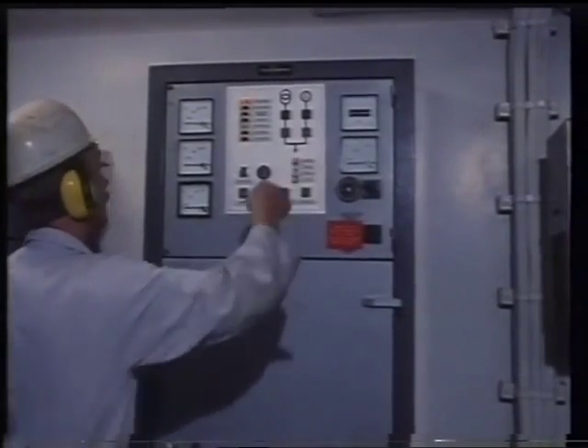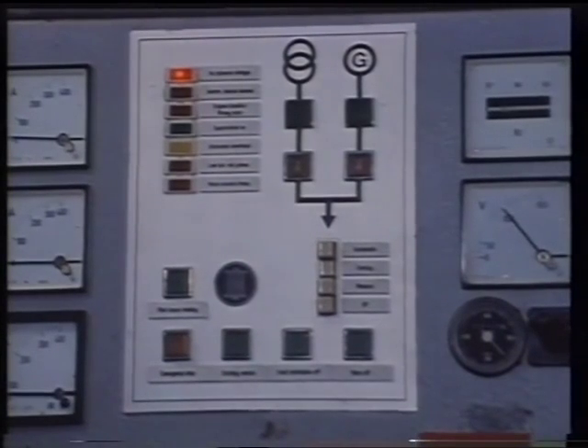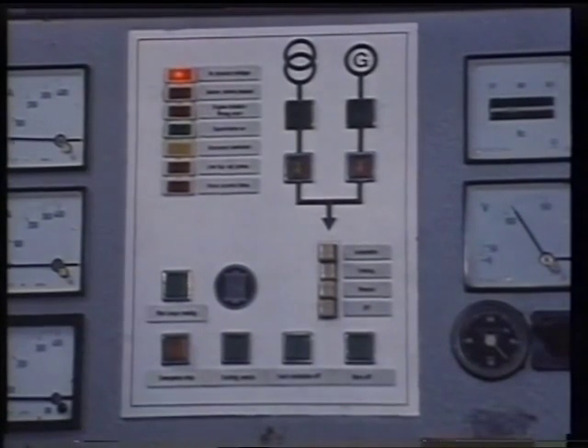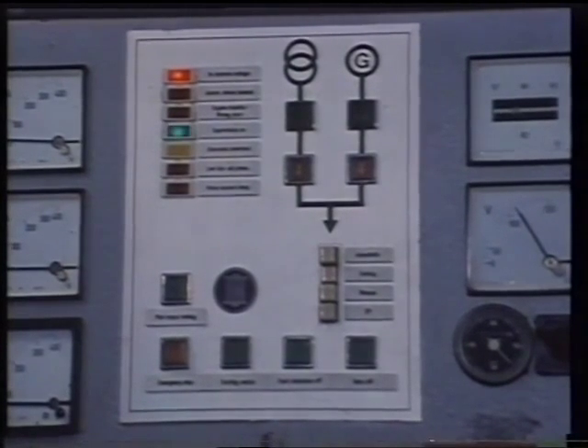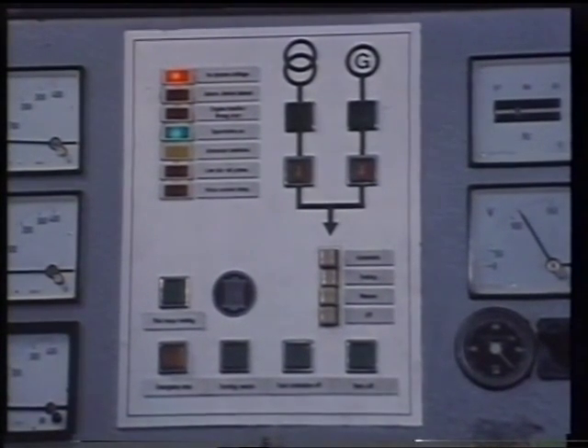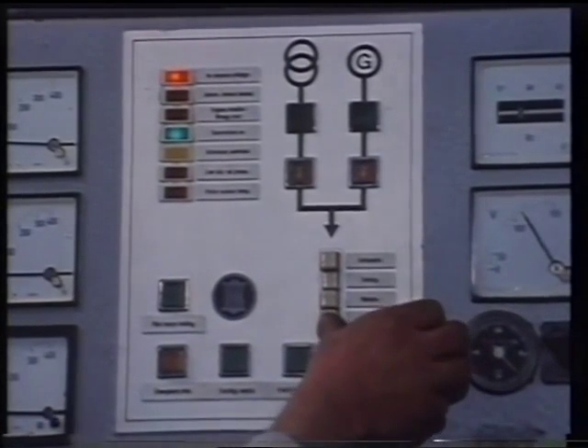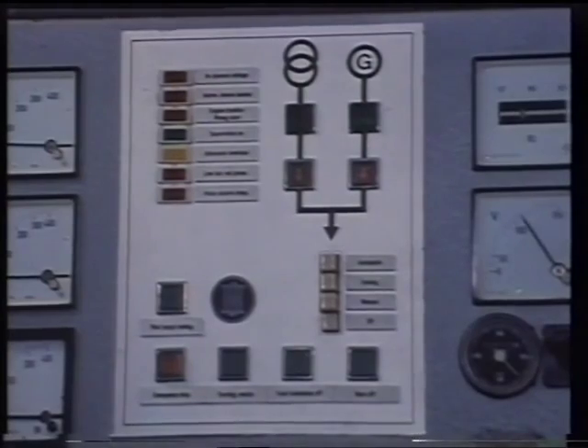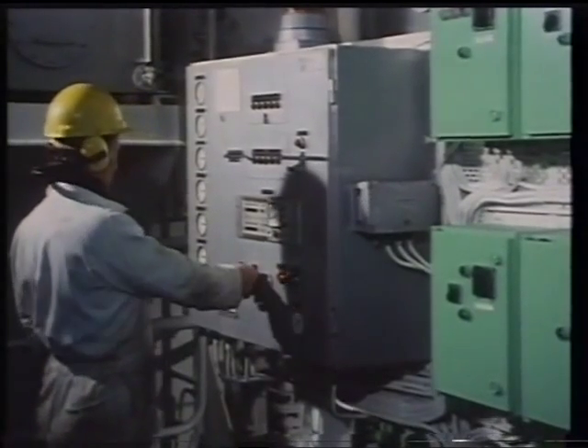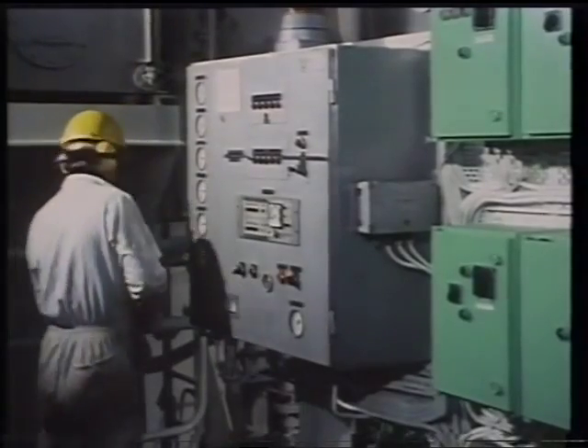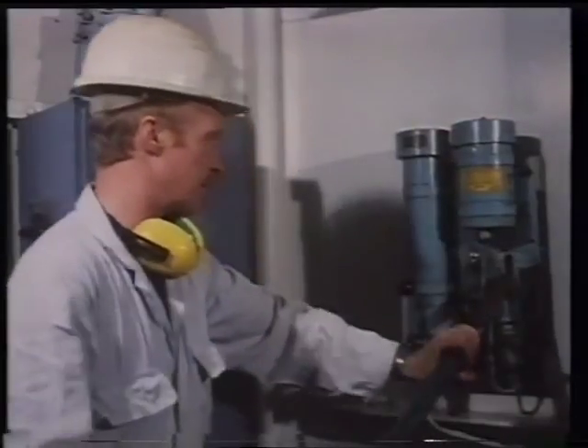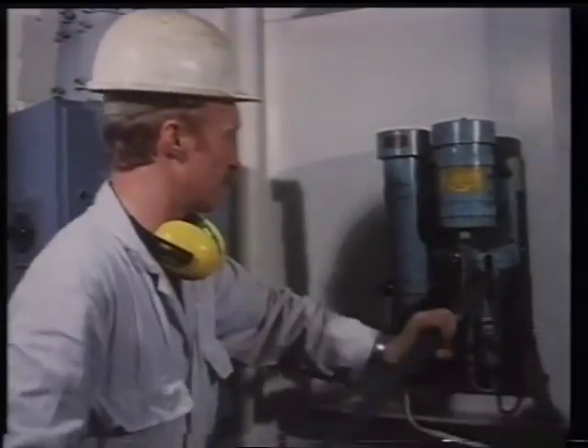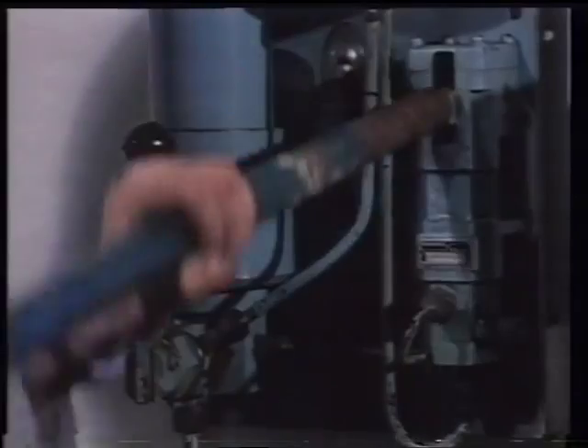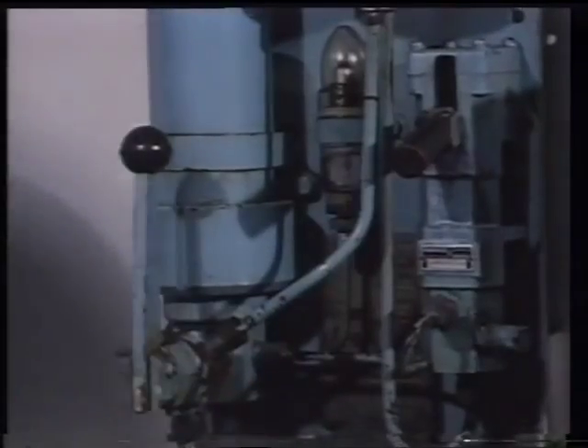The starting system must be tested regularly with the alternator and a load, such as a fire pump motor, connected to the emergency switchboard. The system shown here is a 110-volt system and has its own testing circuit incorporated. Engine starting may be by battery, air pressure, hydraulic, or inertia initiated. Check your own ship's diagrams for specific circuit details relating to your auto-start equipment.